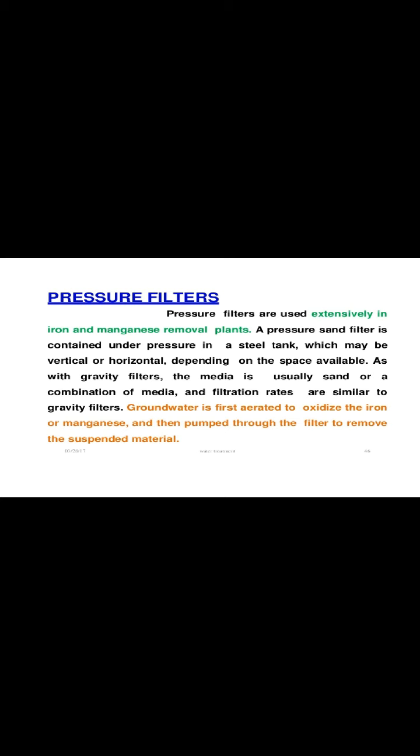Pressure filters are another type of rapid filter. Pressure filters are used especially in iron and manganese removal plants. The pressure sand filter is contained under pressure in a steel tank, which may be vertical or horizontal depending on space available. The filtration media is usually sand or a combination of media, and filtration rates are similar to gravity filters. Groundwater is first aerated to oxidize the iron and manganese, then passed through the filter to remove suspended materials.